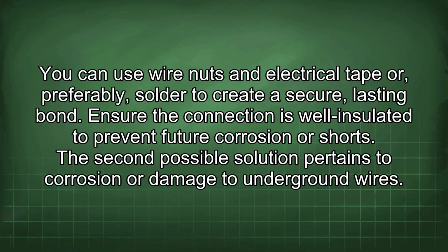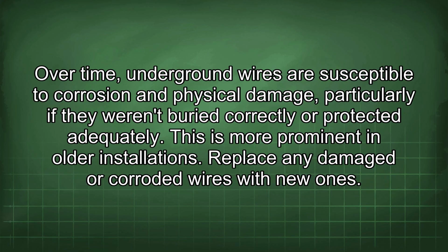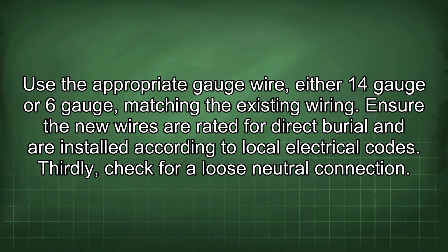The second possible solution pertains to corrosion or damage to underground wires. Over time, underground wires are susceptible to corrosion and physical damage, particularly if they weren't buried correctly or protected adequately. This is more prominent in older installations. Replace any damaged or corroded wires with new ones. Use the appropriate gauge wire, either 14-gauge or 6-gauge, matching the existing wiring. Ensure the new wires are rated for direct burial and are installed according to local electrical codes.